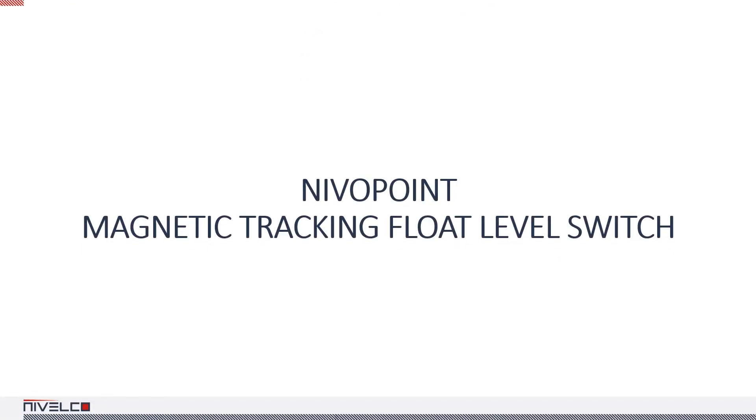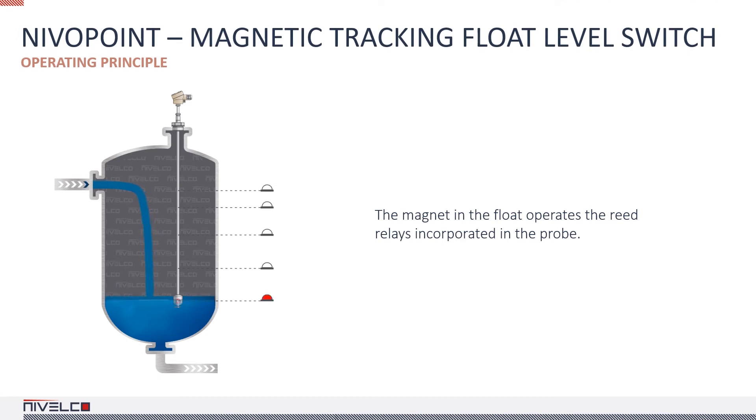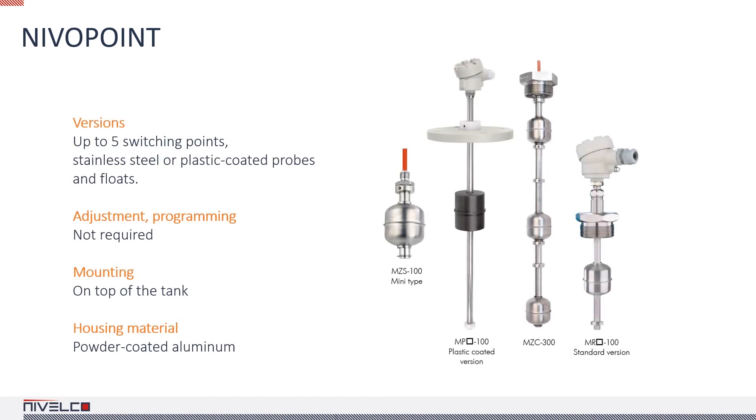NIVOPOINT magnetic float level switches are suitable for single and multipoint level controlling tasks in hazardous and non-hazardous environments. The device consists of a probe tube, a float incorporating a magnet, and a housing that contains the connection terminals. The contacts of the magnetically biased reed relays integrated into the probe are toggled by the float as it passes, and they maintain the last state until the float passes them in the opposite direction. Up to five relays can be integrated into one probe. The position of the relays is determined by strict rules and cannot be changed afterwards. The housing is made of aluminum, and the probe and float are made of stainless steel. The float is available in PP and PVDF, and PFA-coated versions are available as well.